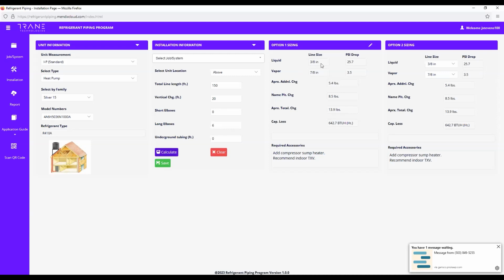It's going to tell you what size to use, 3/8 or 7/8 over here. And then on this side, it'll be blank, but you can populate the size that you want. See how we changed that to 5/16 and it went to yellow? That means it's a big caution. Don't use 5/16. Okay. We'll change this back to 3/8. If we selected 5/8, it goes to red. Pressure drop's too high, so don't use it.